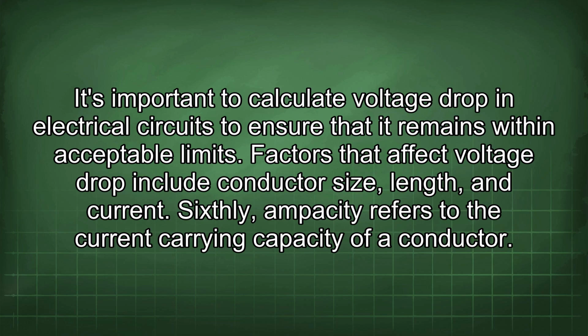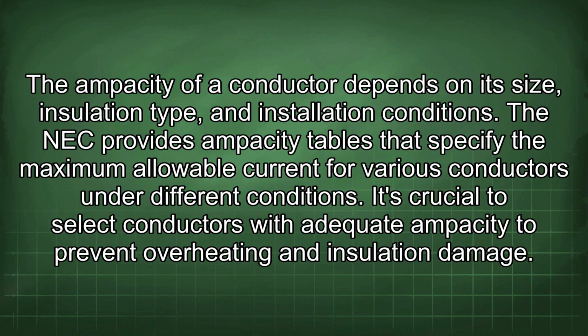Sixthly, ampacity refers to the current carrying capacity of a conductor. The ampacity of a conductor depends on its size, insulation type, and installation conditions. The NEC provides ampacity tables that specify the maximum allowable current for various conductors under different conditions. It's crucial to select conductors with adequate ampacity to prevent overheating and insulation damage.